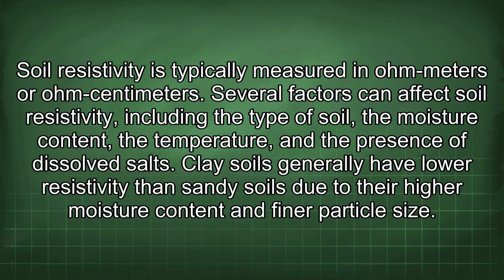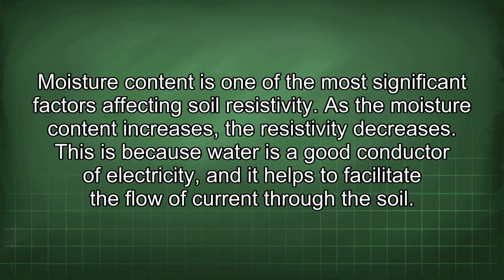Several factors can affect soil resistivity, including the type of soil, the moisture content, the temperature, and the presence of dissolved salts. Clay soils generally have lower resistivity than sandy soils due to their higher moisture content and finer particle size. Moisture content is one of the most significant factors affecting soil resistivity. As the moisture content increases, the resistivity decreases. This is because water is a good conductor of electricity, and it helps to facilitate the flow of current through the soil.